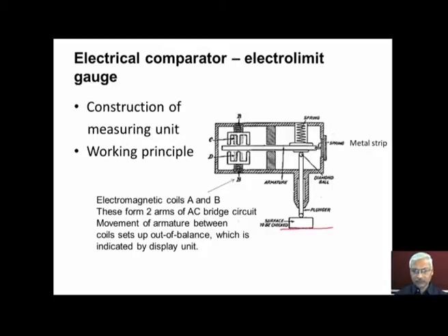This is the surface plate or table on which we have to place the workpiece. We have to insert the workpiece between the plunger and the table surface. Now, depending upon the height of the workpiece, the plunger will move up and down. If the height of the workpiece is greater than the desired height, the plunger will move up. If the height of the workpiece is lower than the desired height, then the plunger will move down. And then we have an armature which is supported by metal strip springs here.